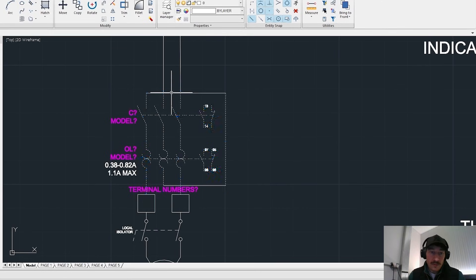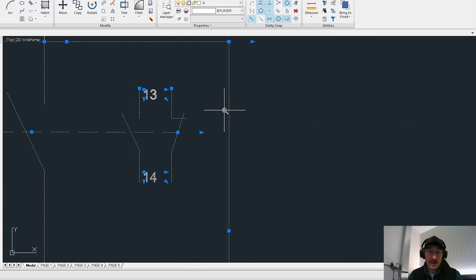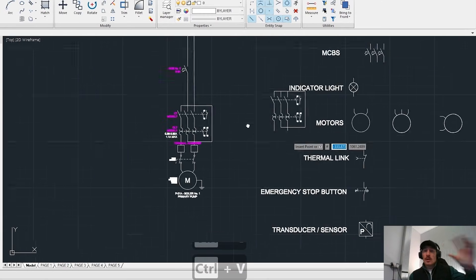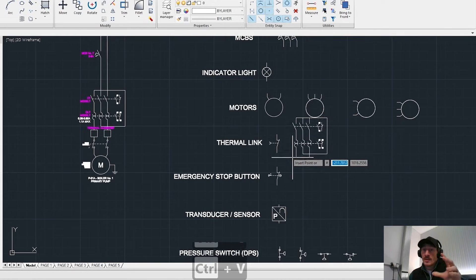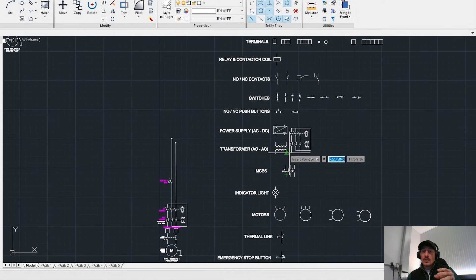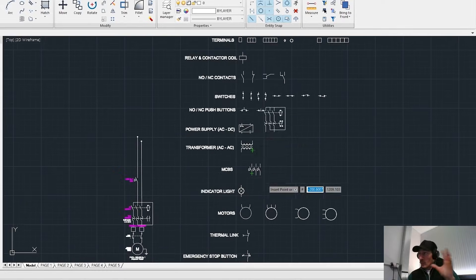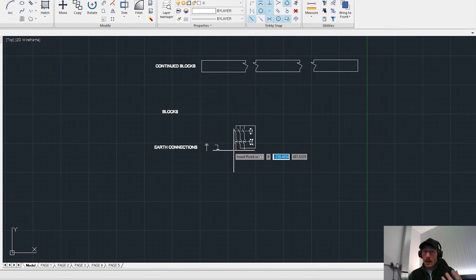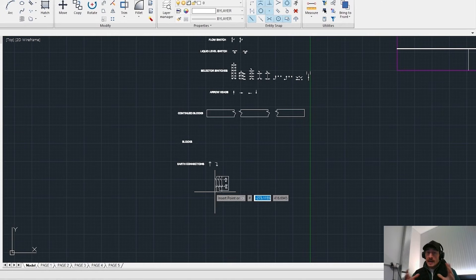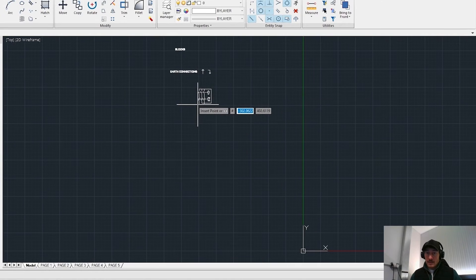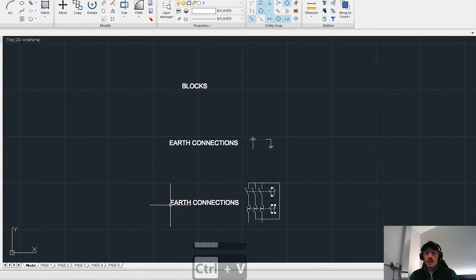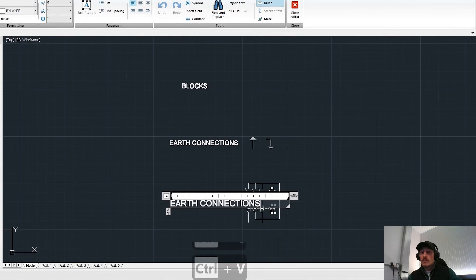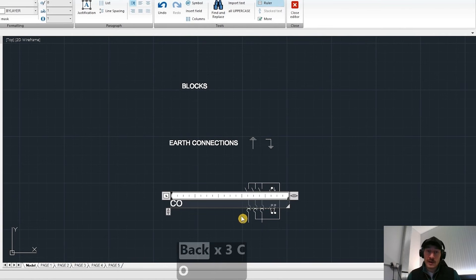Now for anyone that is unfamiliar with what this is here, the C question mark and the OL question mark is contactor and overload. So we are using a contactor and overload now for the control of what you will see are our dumb pumps. These are what I class as dumb pumps. There is no intelligent electronics built into the pump. So we are just going to use pretty bog standard old school control, using a contactor and overload configuration.